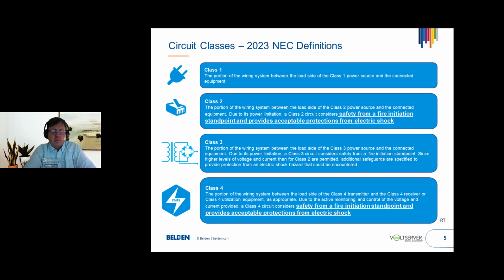Class 4 is a little different. The definition here is the portion of the wiring system between the load side of a Class 4 transmitter and a Class 4 receiver or Class 4 utilization equipment as appropriate, due to the active monitoring and control of the voltage and current provided. A Class 4 circuit considers safety from a fire initiation standpoint and provides acceptable protections from electric shock. The reason I have those two phrases underlined and in bold is because they're both the same context. They're both as safe from fire initiation, and both are as safe from electric shock.